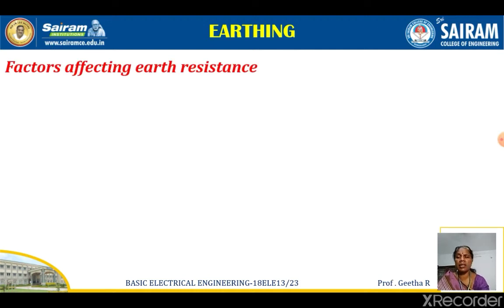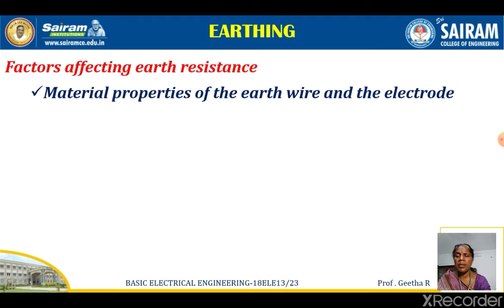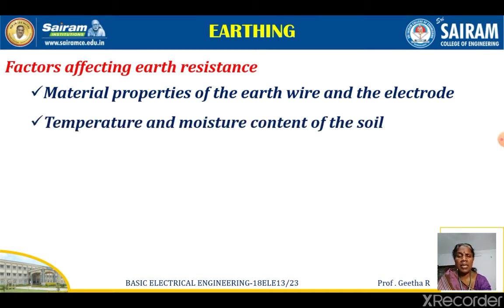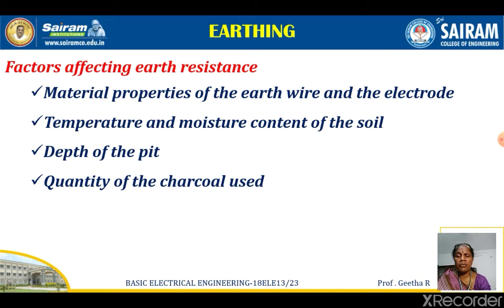Factors affecting earth resistance: the material properties of the earth wire and the electrode, temperature and moisture content of the soil, depth of the pit, and quantity of charcoal used. All these are factors that affect the earth resistance, so attention must be given so that the earth resistance is not increased.